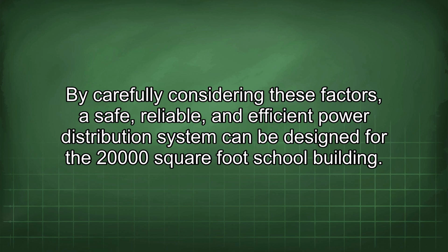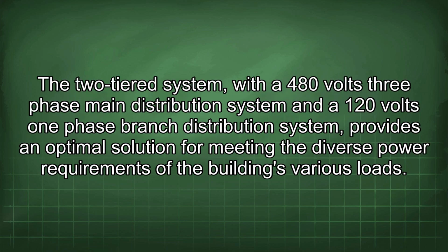By carefully considering these factors, a safe, reliable, and efficient power distribution system can be designed for the 20,000 square foot school building. The two-tiered system with a 480 volts 3-phase main distribution system and a 120 volts 1-phase branch distribution system provides an optimal solution for meeting the diverse power requirements of the building's various loads.